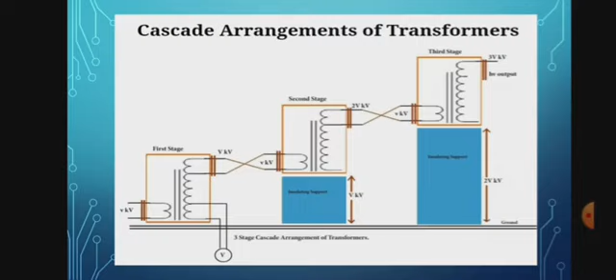The figure shows the cascade transformer connections, in which the first transformer is at the ground potential along with the tank. The second transformer is kept on insulators and maintained at the potential of V2, the output voltage of the first unit above the ground. The high voltage winding of the first unit is connected to the tank of the second unit. The low voltage winding of this unit is supplied from the excitation winding of the first transformer, which is in series with the high voltage winding of the first transformer at its high voltage end.